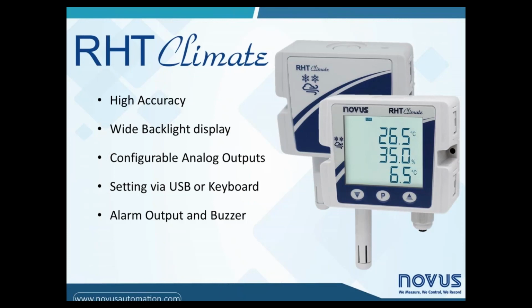Those are configurable by software, including the hardware output signal, which can be 4-20 milliamps or 0-10 volts. We'll see later in the technical characteristics that it's possible to force a certain value to the output for commissioning tests.